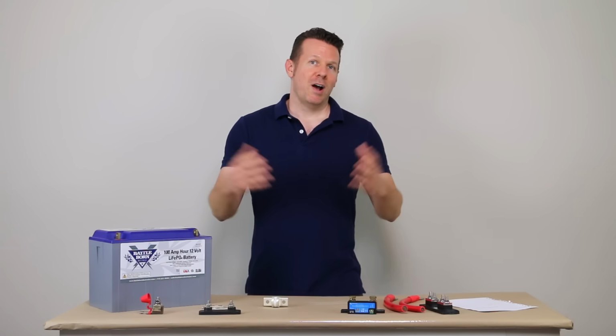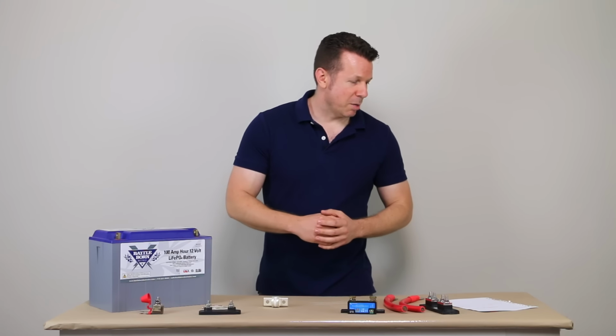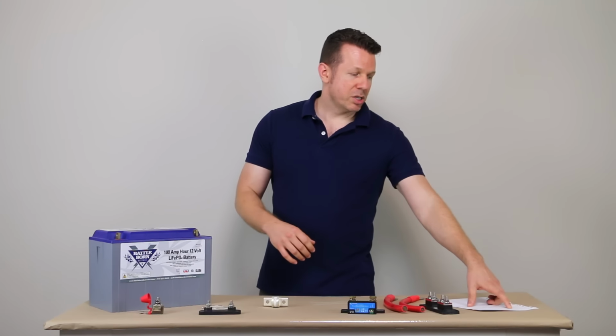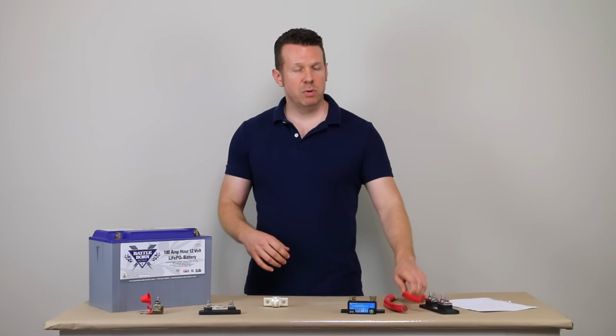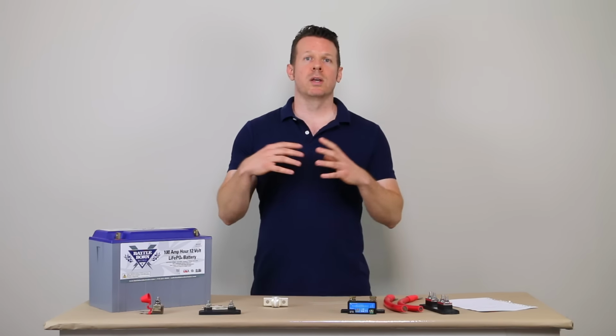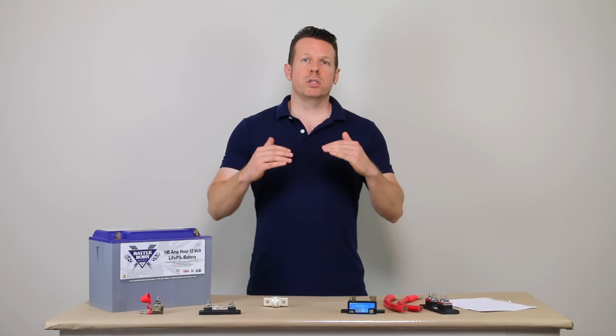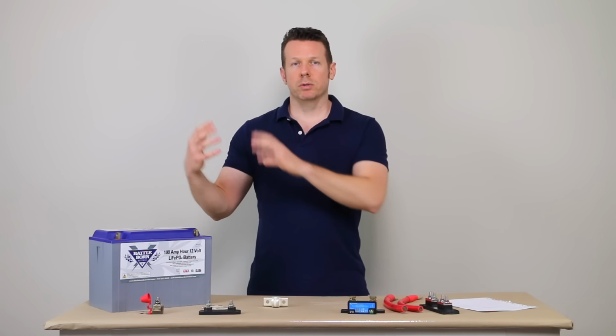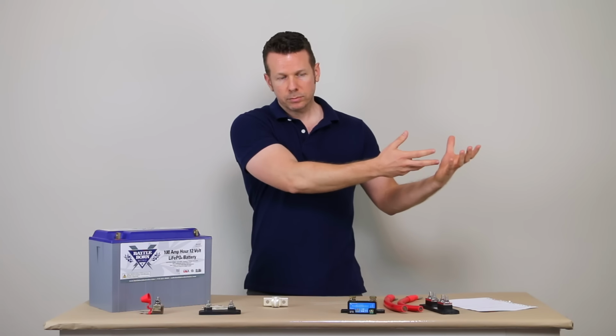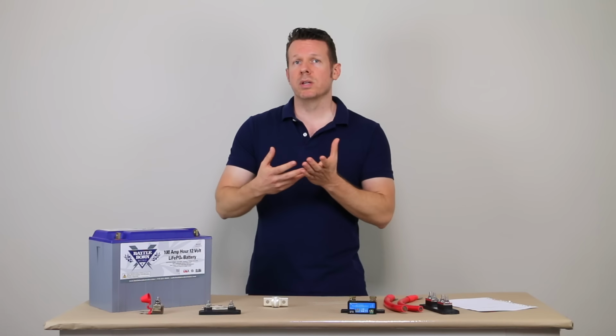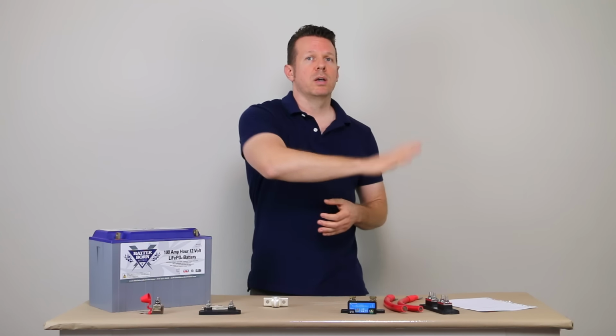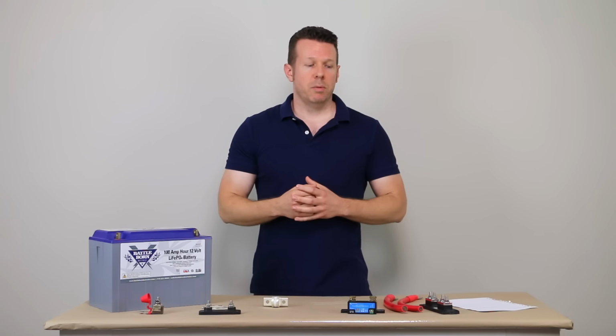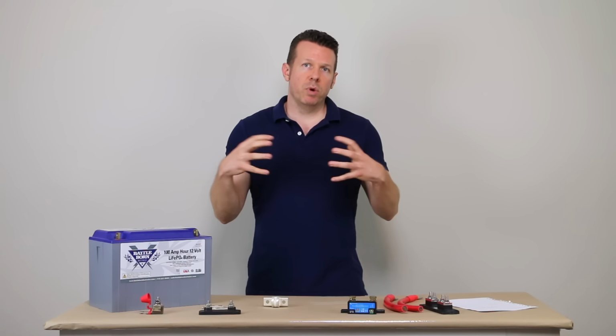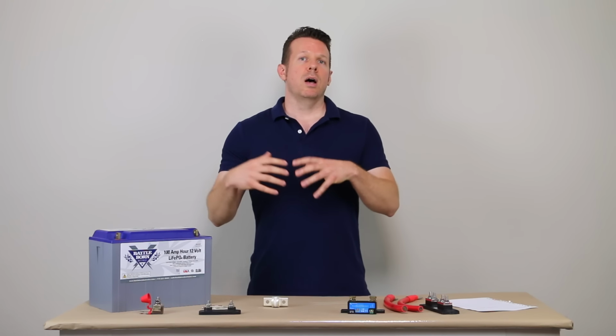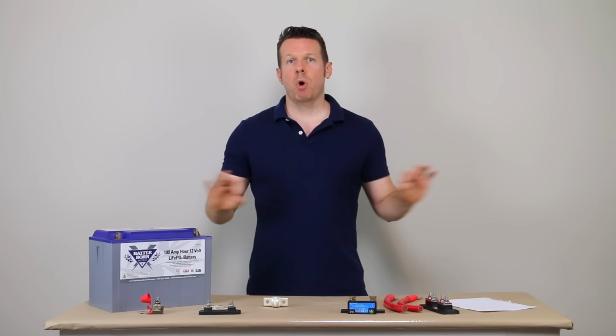All right, with that, let's move on to mistake number 2. This is small cables causing DC ripple. So DC ripple is kind of like a vibration in your system that is caused when you have an inverter. The inverter is taking DC power from the batteries and turning it into AC power, alternating current power. And that causes kind of a ripple in the lines, and that is exacerbated if you have smaller cables.